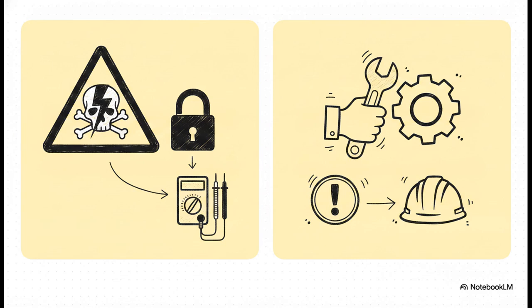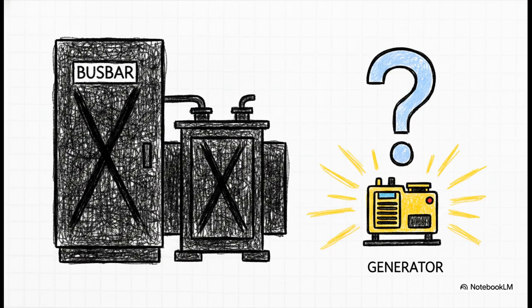Now, we really need to clear something up, because this is a massive myth. In the marine engineering world, 440 volts and 230 volts are officially classified as low voltage. But do not mistake low voltage for low hazard. These motor control centers distribute real, fault-capable current that is absolutely lethal. You can never, ever assume an MCC breaker is safe to work on without independent verification. We're talking strict lockout, tagout, and voltage testing. It demands immense respect.